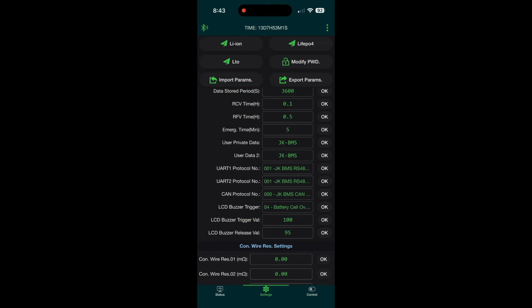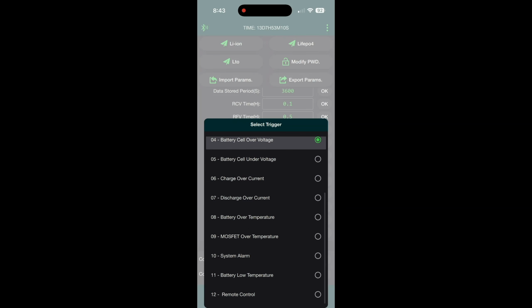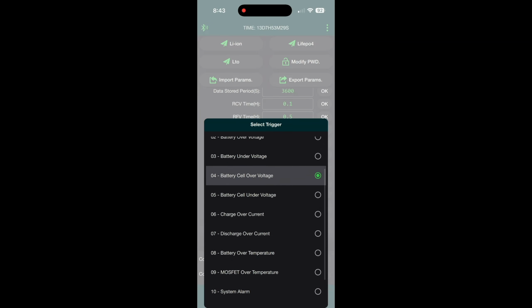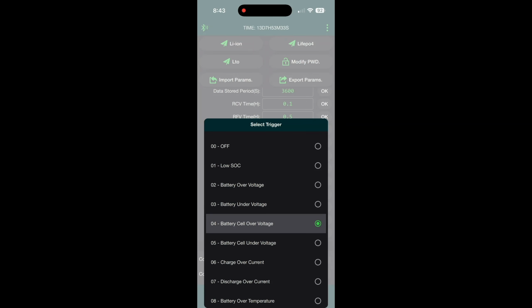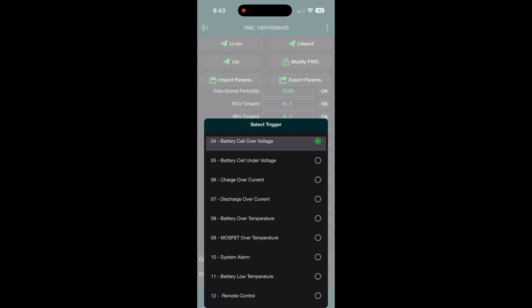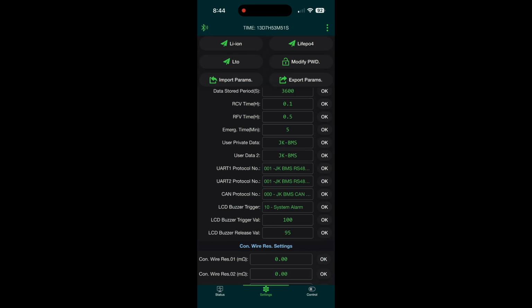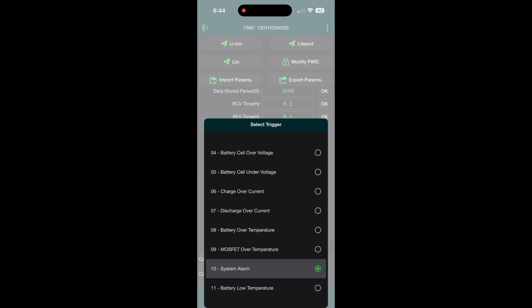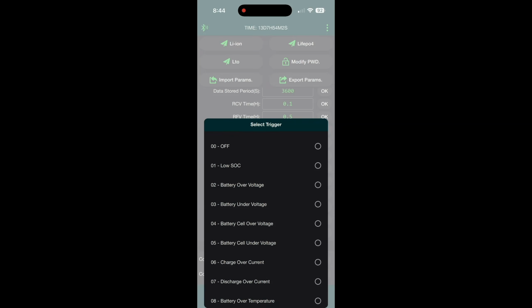Moving down to the LCD buzzer trigger. With the JK BMS, you can set it up so that it has an audible buzzer, and you can even set up a screen so that if there's an issue with the battery, it will sound an alarm. There's a number of different options here that you can set if there is an issue - for example, low voltage SOC (state of charge), battery over voltage, battery under voltage. You can see there's a number of alarms you can set. Then there's number 10, which my understanding is that's for any system alarm - high voltage, low voltage, or anything - that will trigger the alarm. Or you can be specific about any one you want to select. 00 is just off. I don't have a buzzer connected, so I'm happy to leave that as off.